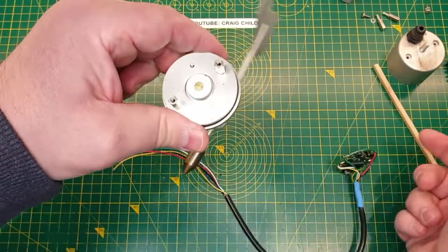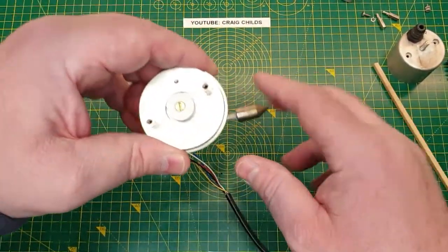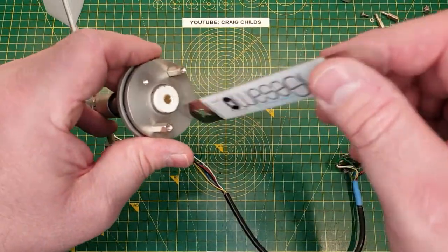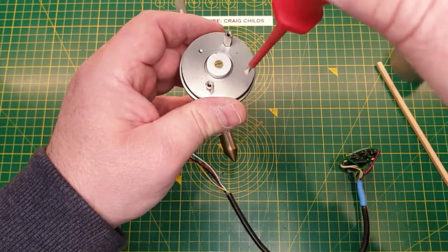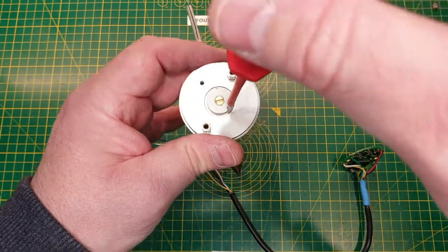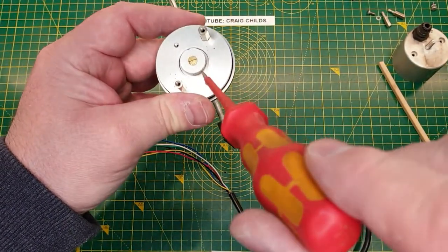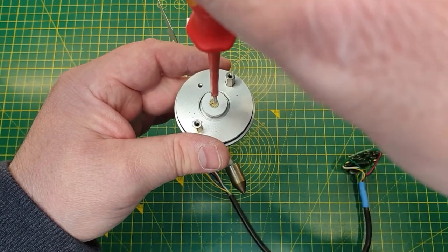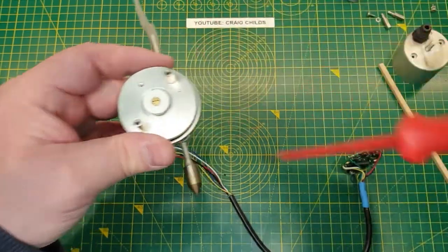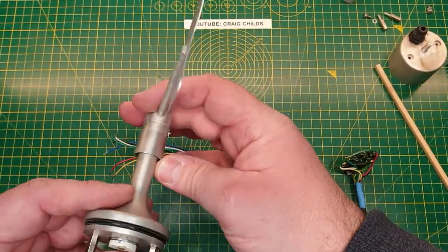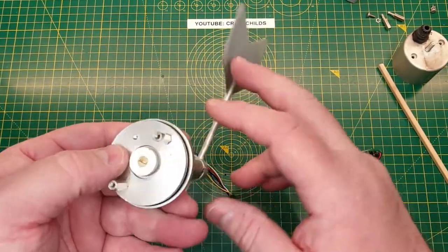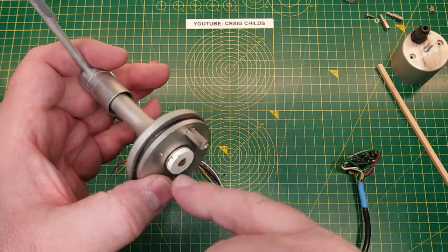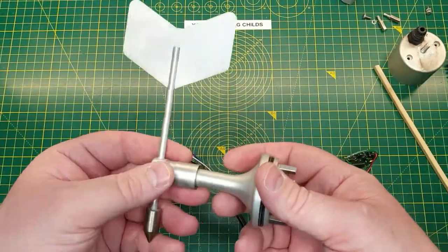So what we have here is, again, you've got a rotating shaft. When it comes down through, this bit rotates here. This bit is a magnet. Let's see if we've got something that's—yep, magnetic. So it's polarized in fact. See how the tip of the screwdriver's drawn to one end of the magnet, so it's either north or south here. Now again that's important, and if I was to take that off there probably are markings on here for reassembly, but possibly not. I mean effectively you don't want to take this off. If you are going to take it off, you know, if you've got one of these and you're going to take it off, put a mark on it before you do that because otherwise your rotation's going to be wrong.